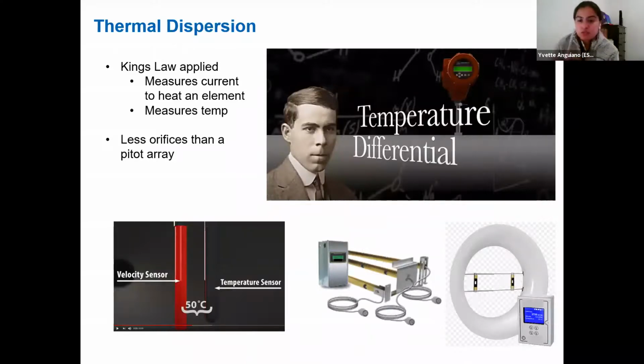So digging into thermal dispersion, which you may also know as a hot wire anemometer. In this lower left-hand side picture, we're depicting this temperature sensor element right here, which is serving as our reference temperature. And then you've got this heating element a little distance away to the left. The device is keeping a constant delta T between those two devices. Depending on how fast the media flowing through this device is moving, it requires more or less current to keep that delta T constant. And that current is directly proportional to the flow of the media.